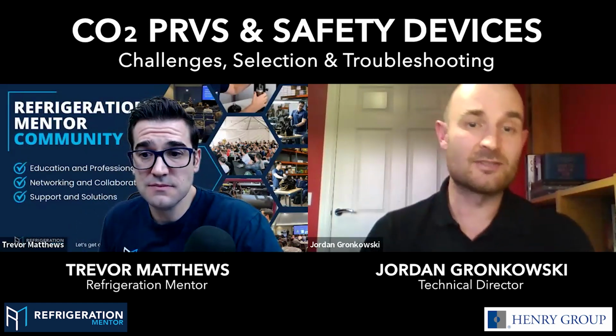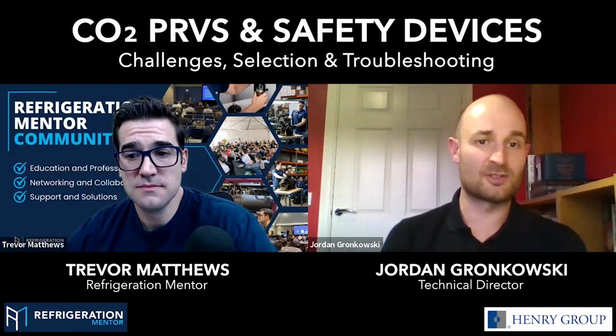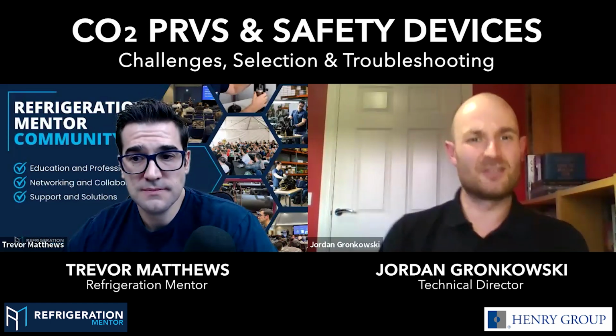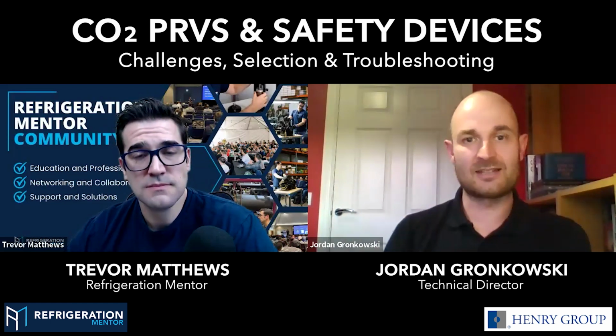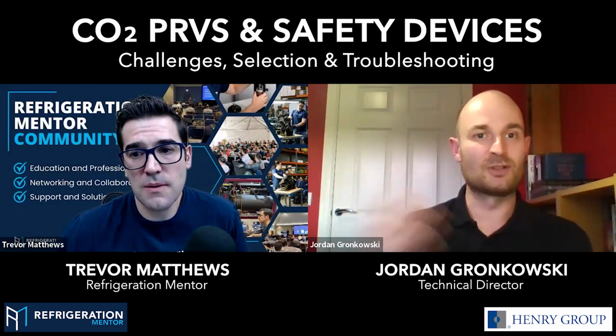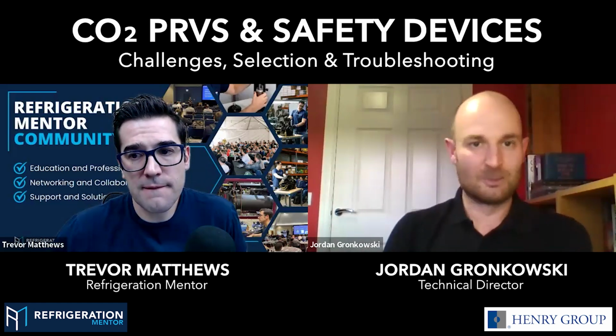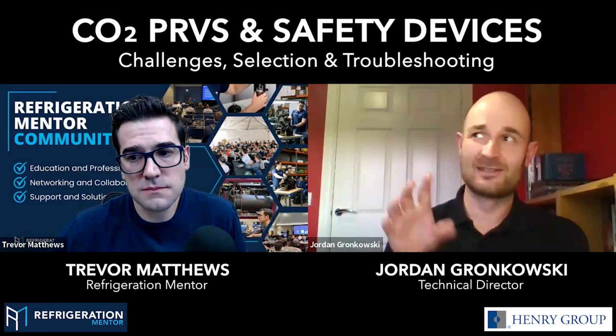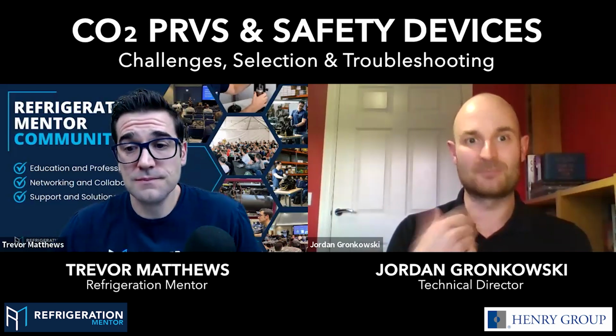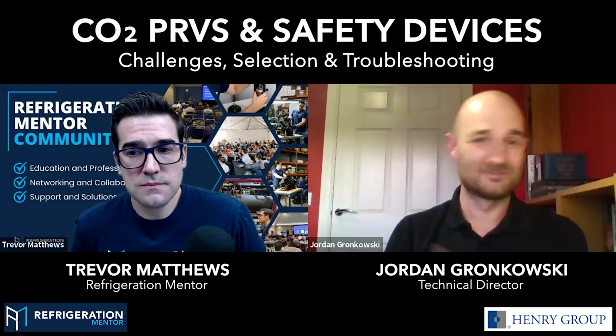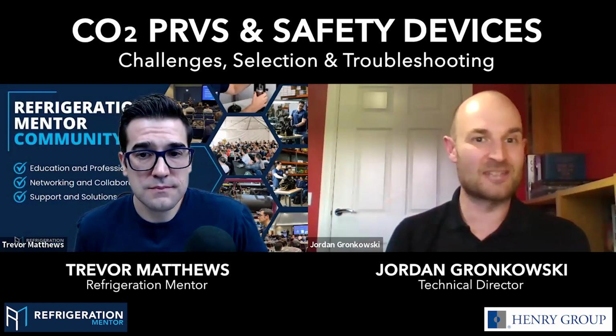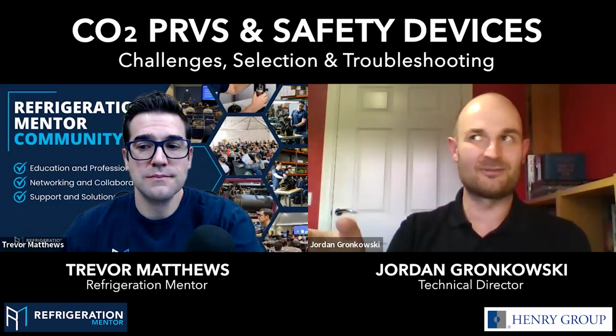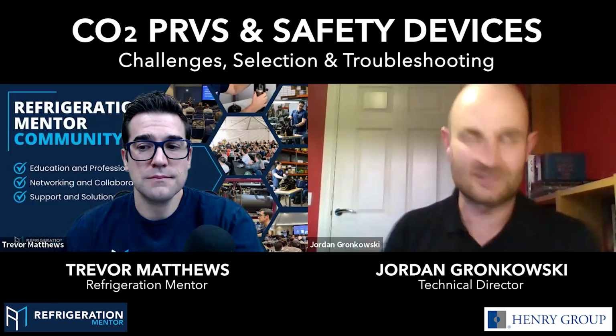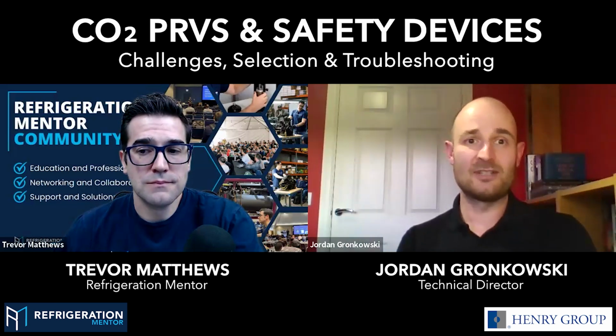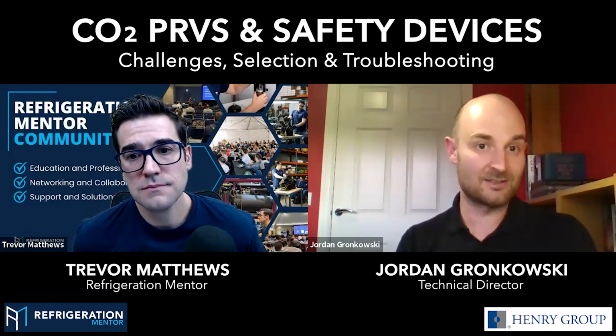No, it's the same here. And EN 378 is our standard, and again, it says PRVs should be isolated or removed for system pressure tests. Because you're going to blow the valve if you do. The other thing, maybe to add slightly onto that, is a question we often get asked, and some people have the requirement. It's should I test the valve before I put it on the system to make sure it's working, make sure it's okay? And we always say no. You should never test the valve with a third party, because valves are so sensitive. It's very easy for you to do a pressure test with the best of intentions, but actually the test in itself modifies the set point of the valve, and you can get a false positive and a false negative. And as I said before, every manufacturer has different definitions of what the set point is. So you could be looking for a bubble when the valve from this manufacturer is actually set when you can hear it, or vice versa. So if you have to do a test on a PRV, again, the EN 378 standard says that each valve should be tested for seat tightness before it goes in the system.